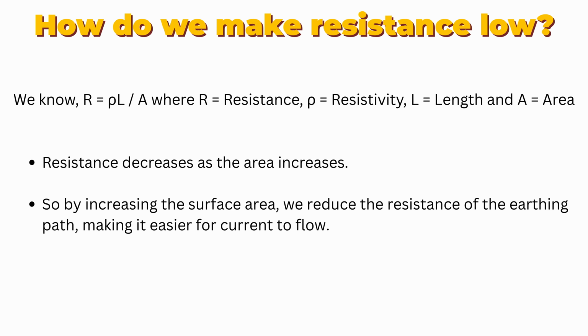Now this is the key idea: resistance is inversely proportional to area. That means if area increases, resistance decreases. So when we increase the surface area, we give current more space to flow, which reduces resistance. That's exactly why in earthing we use large metal plates or long rods in the ground. More area, less resistance, easier current flow.